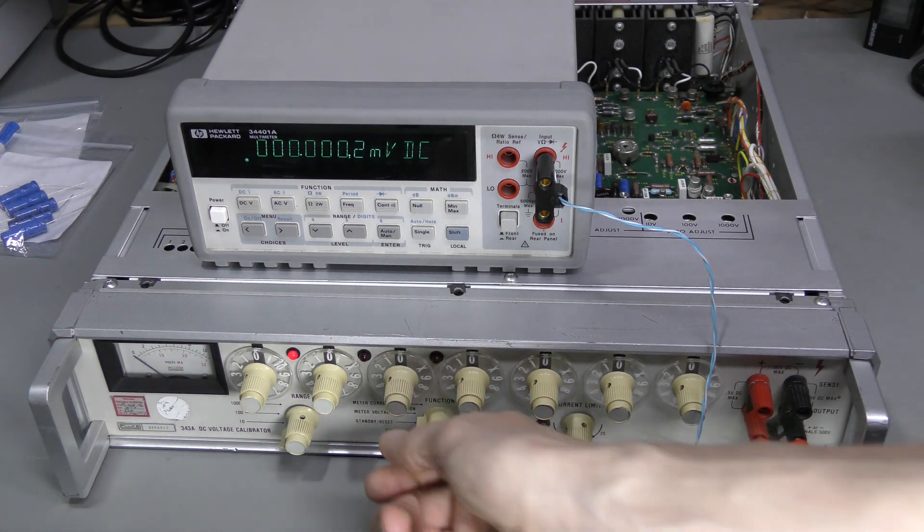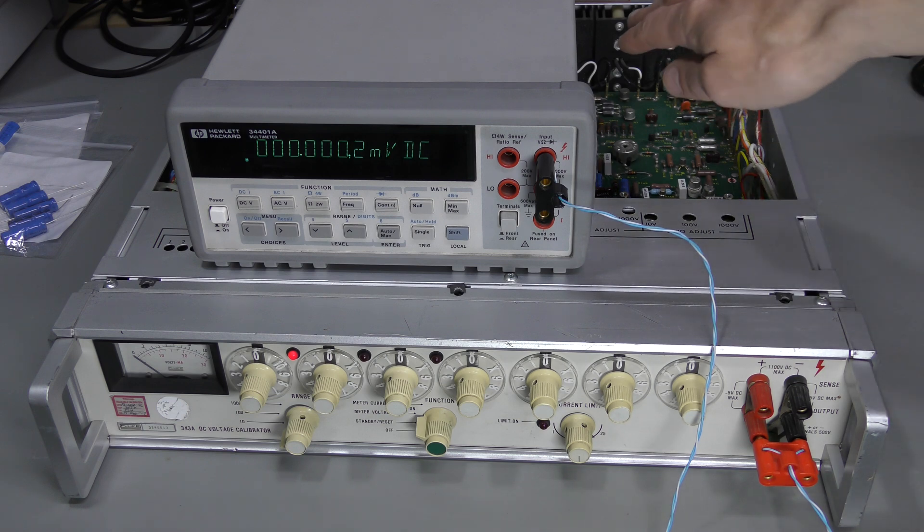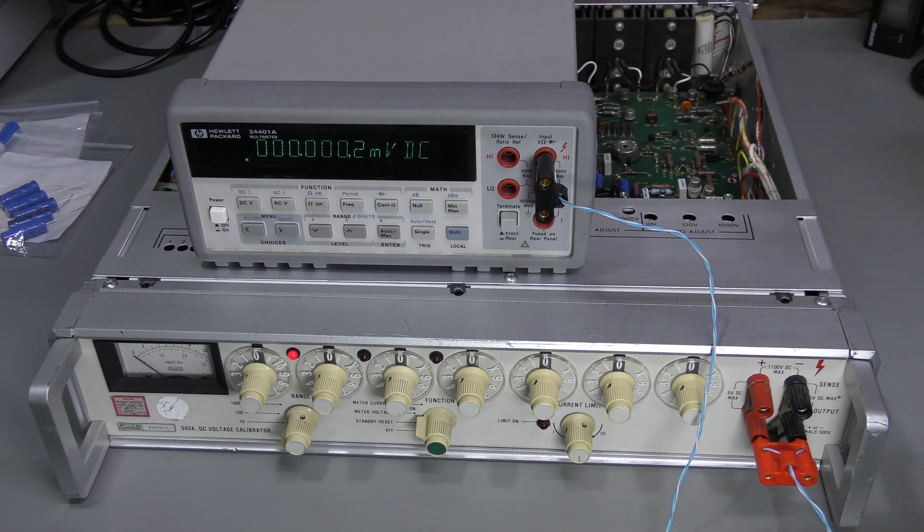I also found that wiggling some switches could change that offset quite a bit. So I cleaned the switches and now I cannot reproduce this anymore. And also the service manual says that adjusting the chopper amplifier is supposed to shift zero point. So I adjusted zero points for all three ranges and now we are good.